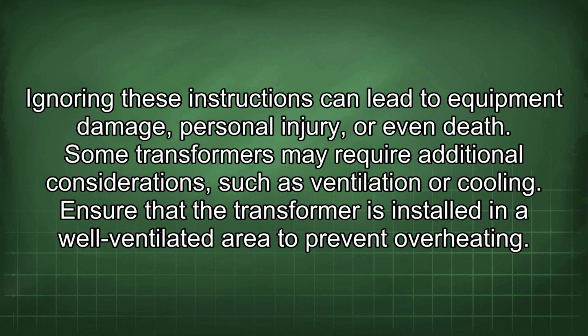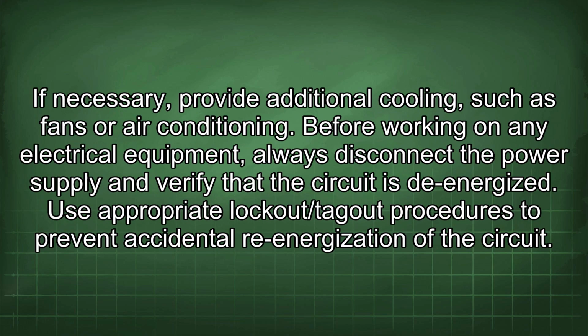Some transformers may require additional considerations such as ventilation or cooling. Ensure that the transformer is installed in a well-ventilated area to prevent overheating. If necessary, provide additional cooling, such as fans or air conditioning.